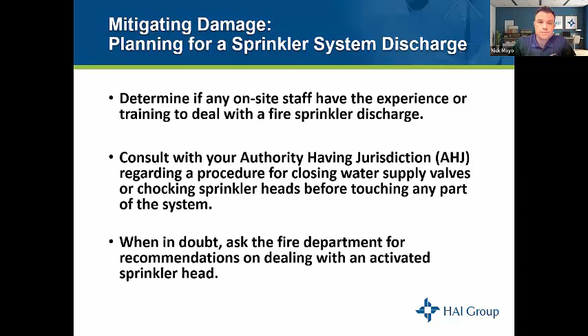So if you're allowed and you're certain that the discharge was accidental, you can control the flow of water from your sprinkler head per your operating procedures. Or on the flip side, you can meet the fire department at the building's front entrance to discuss what happened. If someone is meeting the fire department at the front door and can let them know the floor number, the unit number, or the exact location of the discharge, they'll be able to get up there quicker because they won't have to go to the fire panel to see that it's on the 4th floor, and so on.